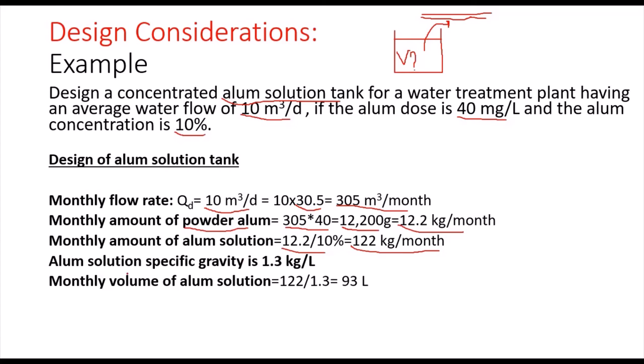We know that the alum solution specific gravity is 1.3 kilograms per liter. So the monthly volume of alum solution will be 122 divided by 1.3. So the volume of my tank will be 93 liters.